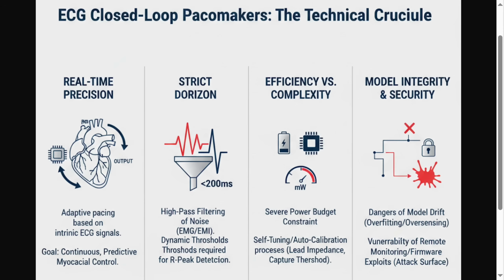The device must continuously monitor lead impedance and the depolarization threshold, the minimum energy required to capture the ventricle. It constantly runs low-level test pulses to find this threshold and dynamically adjust the pacing amplitude. This is essential for battery life. Why waste energy delivering 3 volts when 1.5 volts will do? Wait, so you are confirming that this silicon despot is self-teaching and auto-calibrating inside my body? It's constantly performing micro-experiments to improve its efficiency. This means the pacing parameters, the very thing keeping me alive, are slowly drifting away from the original physician-set parameters. What if the model drifts into a locally optimal, globally fatal configuration?